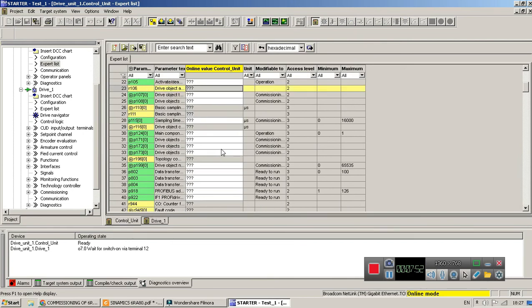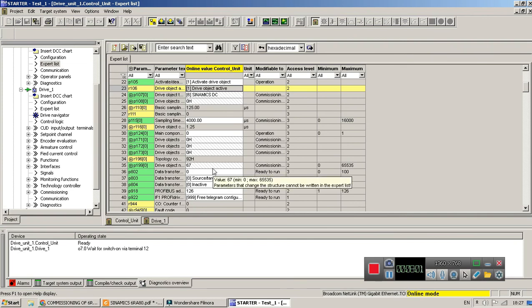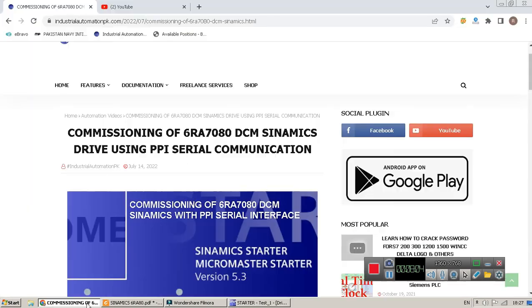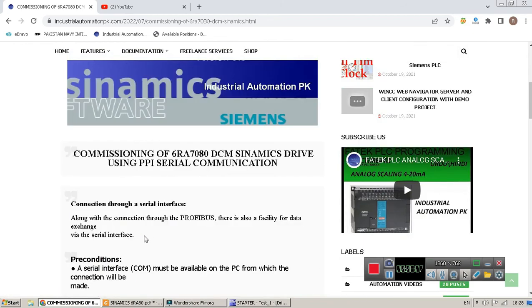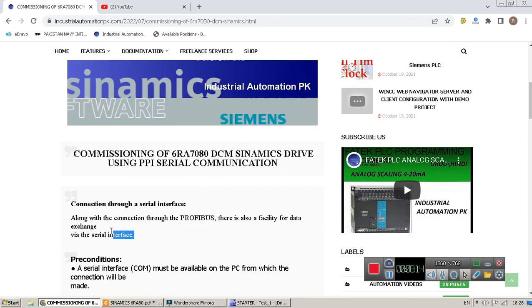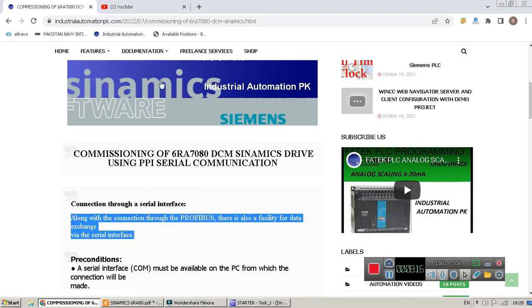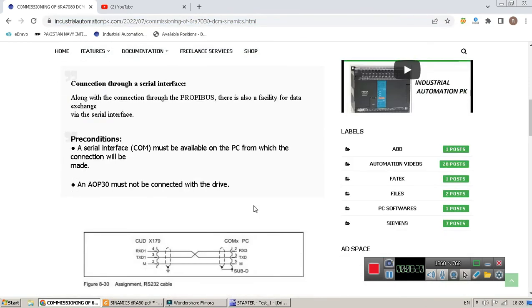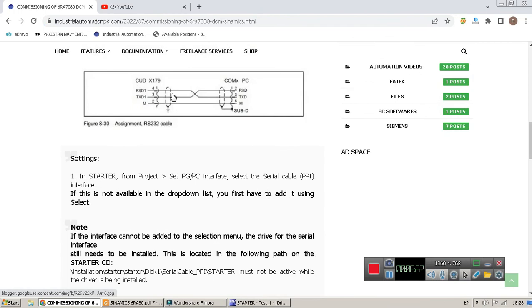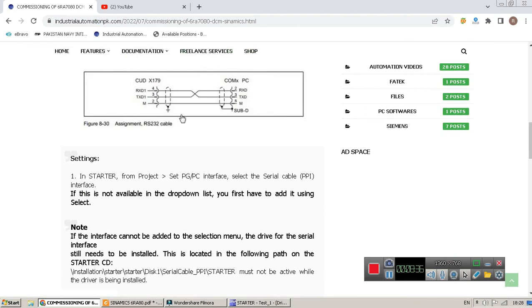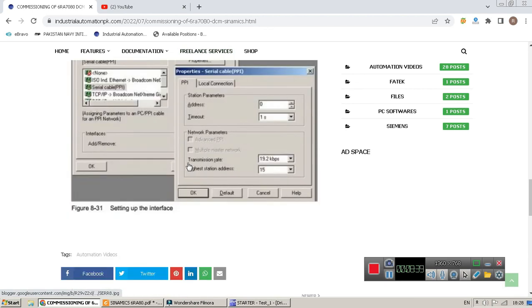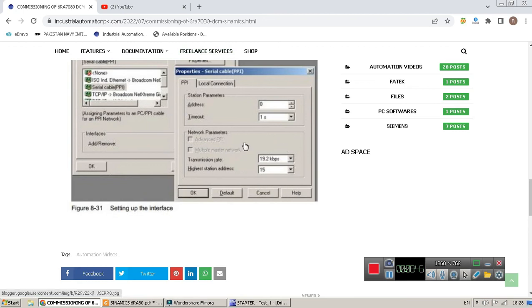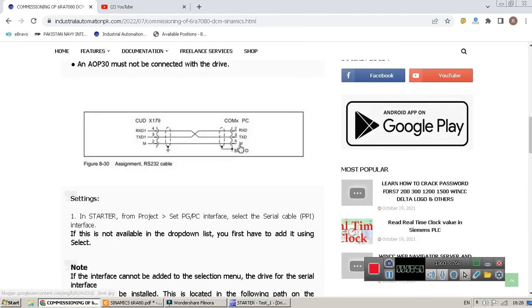So that's how you have to connect and commission your Sinamics DCM drives using serial PPI. And one thing you should remember for serial PPI that you did not use USB to serial converter as it malfunctions your communication and disconnects your communication several times. I have given the following link in the description. Kindly go through and read this. Here I have mentioned how to pin out configuration of CUDX179 PPI terminal and DB9 connector PC side. And I have used PC serial port to communicate this. So this is the PPI serial cable settings. Always remember these settings to get your desired result 100%.